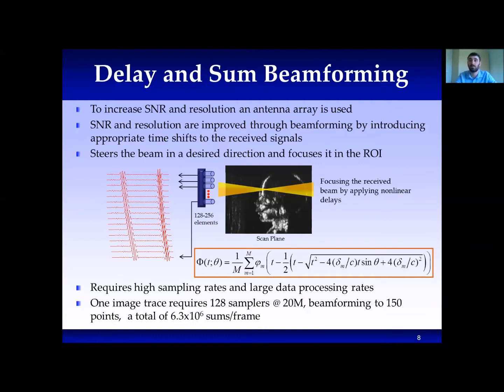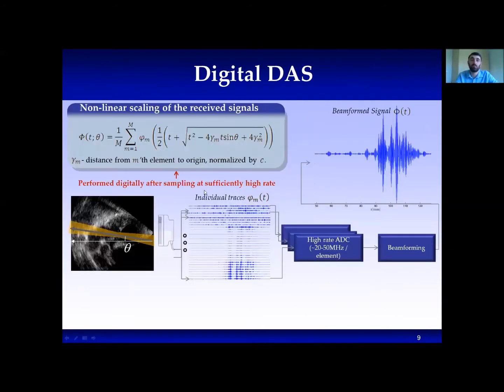However, this method requires high sampling rate and many receiving elements, which results in a huge amount of data and makes ultrasound over Wi-Fi almost impossible. The pulse is transmitted to the tissue and the echoes received at each channel are sampled at high rate, typically 8 to 10 times higher than the Nyquist rate of the signal. After sampling the signal, delay and sum is applied digitally, resulting in the beamformed signal.